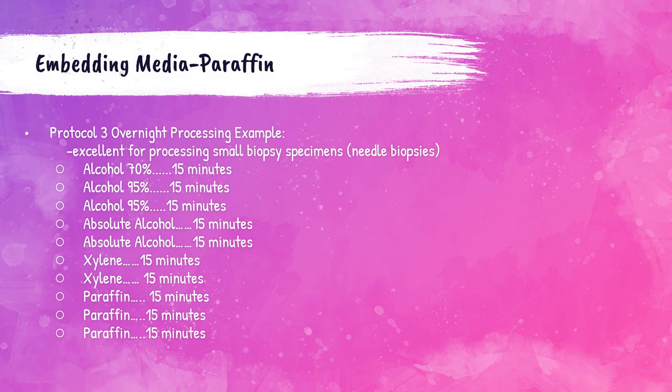Protocol three utilizes vacuum and heat only with paraffin, and is excellent for needle biopsy specimens. This protocol uses 15 minutes of 70% alcohol, 15 minutes of 95% alcohol, another 15 minutes of 95% alcohol, two steps of absolute alcohol at 15 minutes each, two steps of xylene at 15 minutes each, and then three steps of paraffin at 15 minutes each.